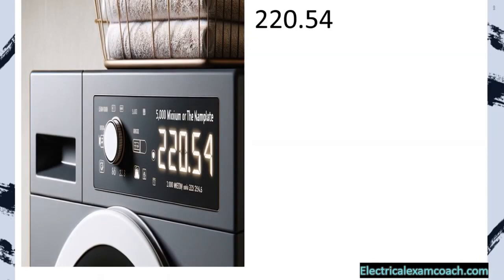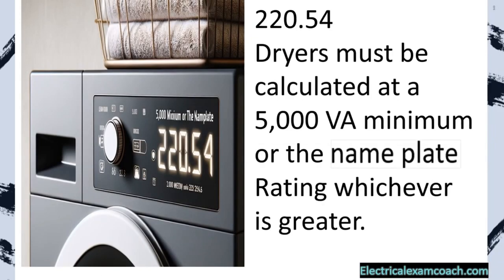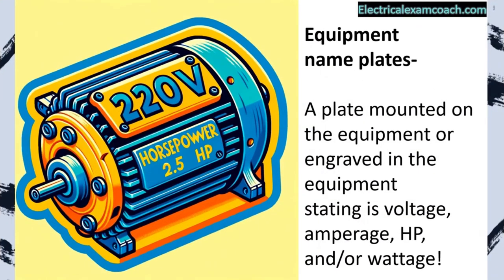Section 220.54 lets us know that dryers must be calculated at a 5,000 VA minimum or the nameplate rating, whichever is greater. A nameplate is a plate mounted on or engraved in the equipment stating its voltage, amperage, horsepower, and/or wattage. As we've learned in previous lessons, we can apply Ohm's Law to find any unknown.